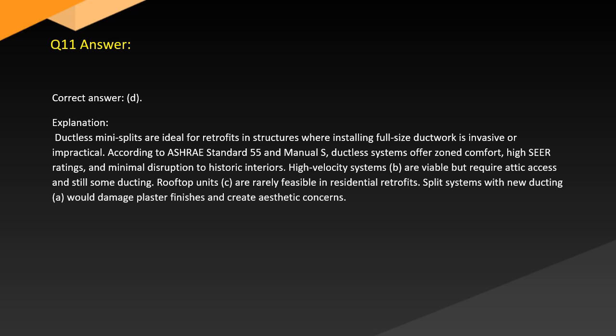Answer. Correct answer: D. Explanation: Ductless mini-splits are ideal for retrofits in structures where installing full-size ductwork is invasive or impractical. According to ASHRAE Standard 55 and Manual S, ductless systems offer zone comfort, high SEER ratings, and minimal disruption to historic interiors. High-velocity systems, B, are viable but require attic access and still some ducting. Rooftop units, C, are rarely feasible in retrofits. Split systems with new ducting, A, would damage plaster finishes and create aesthetic concerns.